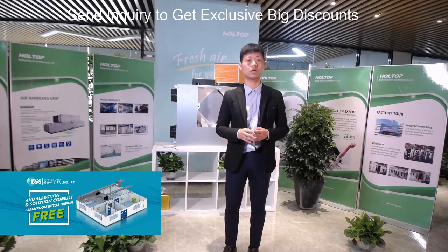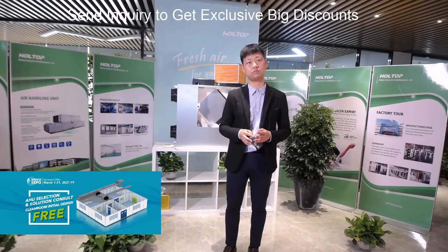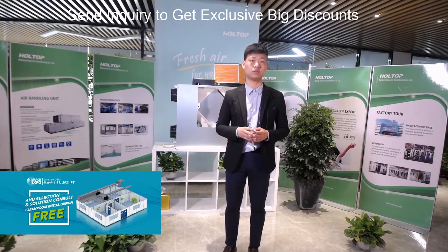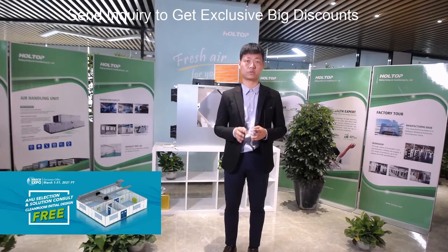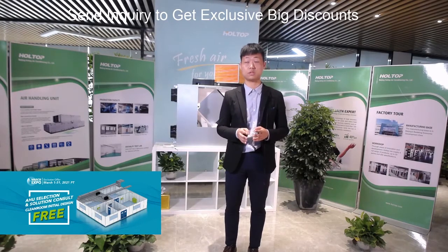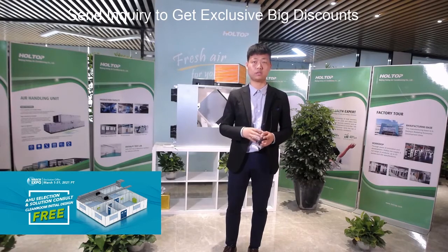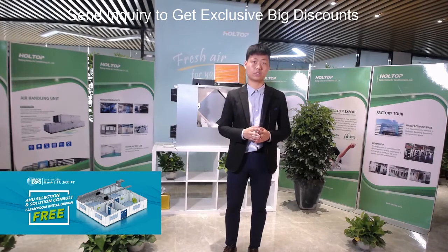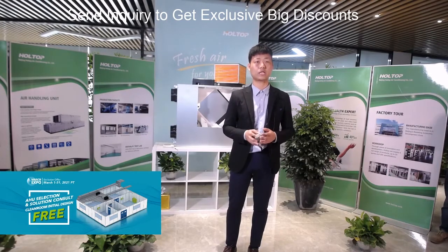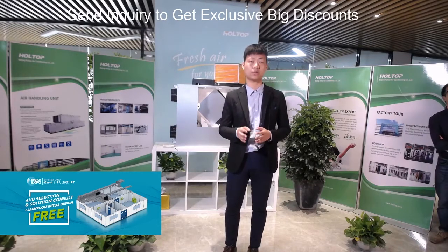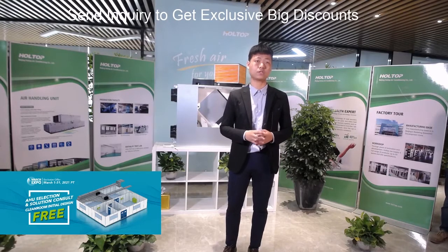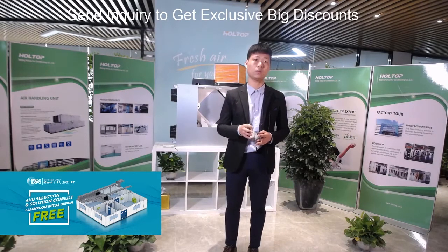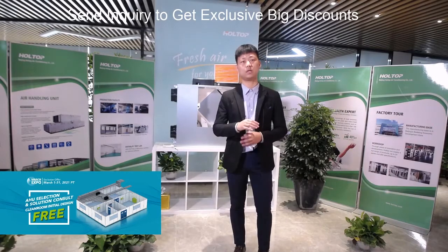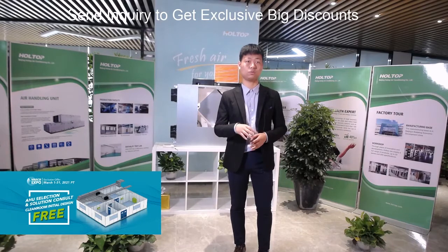Okay. The second one, the key point is how to make the people in the room feel comfortable. One point is we will design the PCR laboratory indoor temperature around 22 to 23 Celsius degrees and 40% to 60% humidity, with enough fresh air supply to each room. The second one is a well-organized airflow pattern. I will show you later about the airflow pattern. The third one is an accurate calculation of the air change rate. PCR lab is constructed according to the cleanroom, ISO, and GMP standards. So we need to consider the reasonable air change rate.